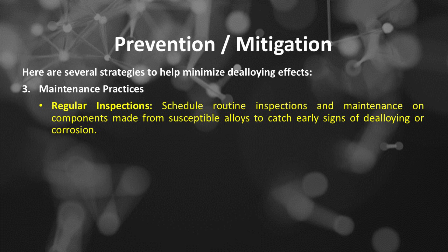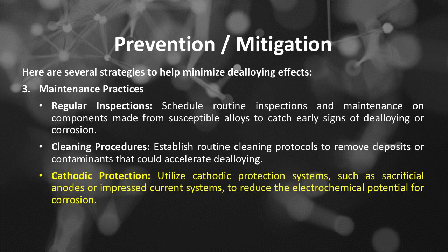Number 3 is maintenance practices. Regular inspections. Schedule routine inspections and maintenance on components made from susceptible alloys to catch early signs of dealloying or corrosion. Cleaning procedures. Establish routine cleaning protocols to remove deposits or contaminants that could accelerate dealloying. Cathodic protection. Utilize cathodic protection systems, such as sacrificial anodes or impressed current systems, to reduce the electrochemical potential for corrosion. Number 4 is design considerations.